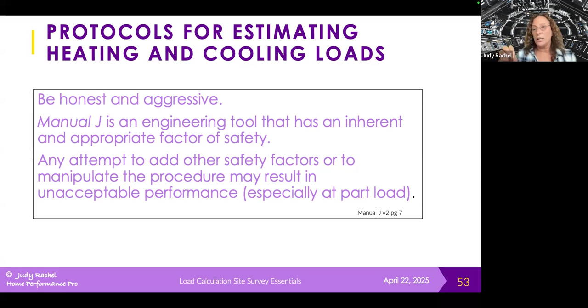So it's not that there is a 15% safety factor built into the Manual J calculation procedure. I hear things like that all the time, that the procedure oversizes by huge amounts, or that there's a safety factor in the procedure. It's more about the way the procedure is put together that has what they're calling this inherent and appropriate factor of safety. So you should feel very confident with the numbers that come out of this procedure, that you're not going to end up undersizing a piece of equipment. And when you're honest and aggressive, you're going to get close enough that you're not way oversizing your piece of equipment either. Okay, so that was my diatribe.